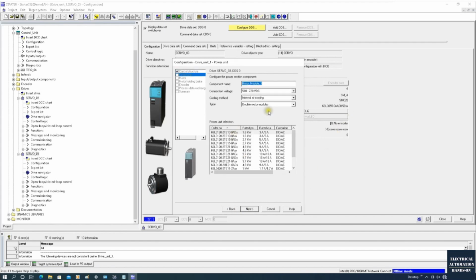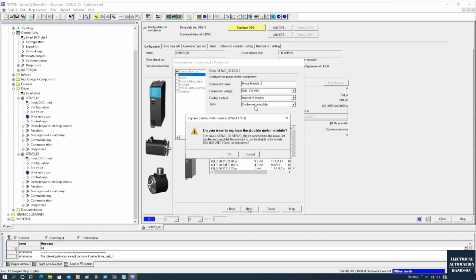The next step is the power unit. The power unit here means the module that connects to the servo motor. In this case, I'm using one module that serves two servo motors. That is the 6SL3120-2TE13. Okay, you can see this is the DC to AC, so this is the motor module, 1.6 kilowatt, and it serves a double motor.